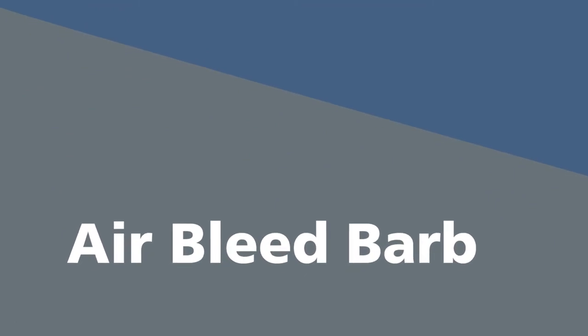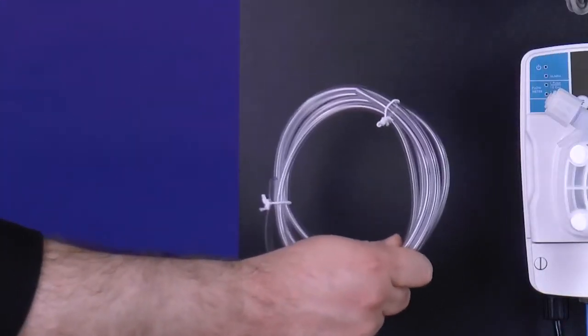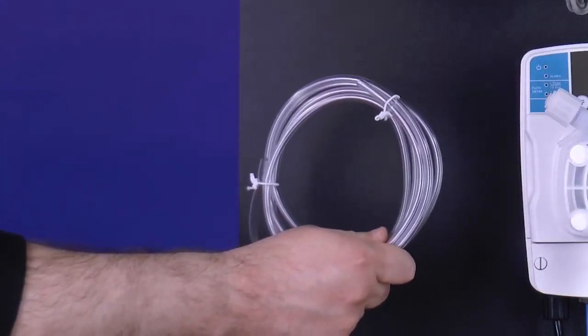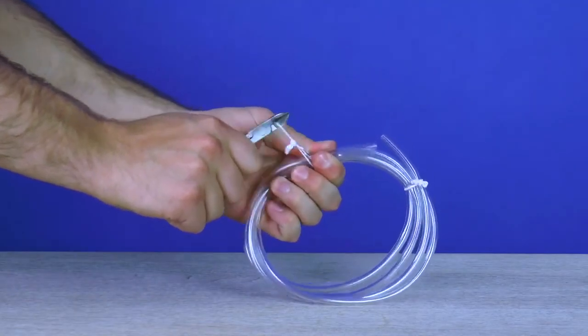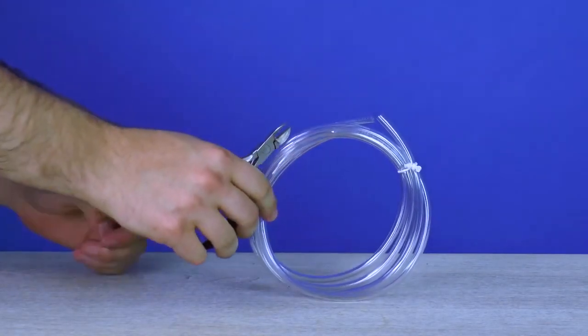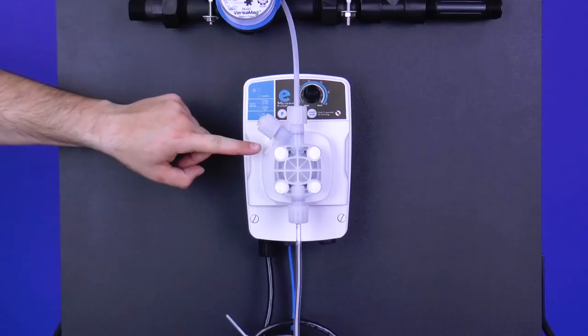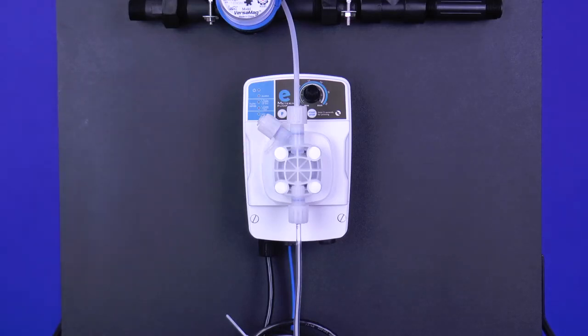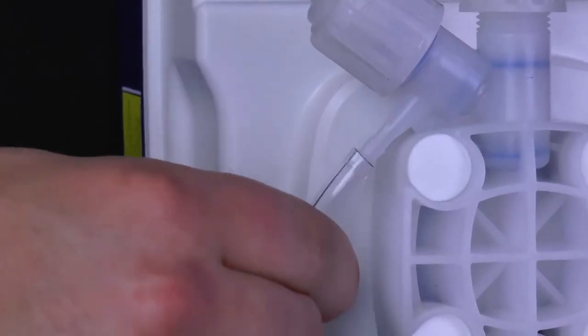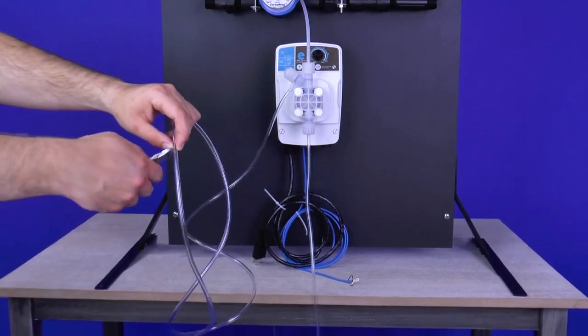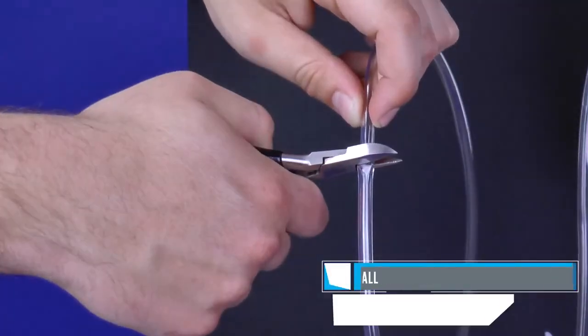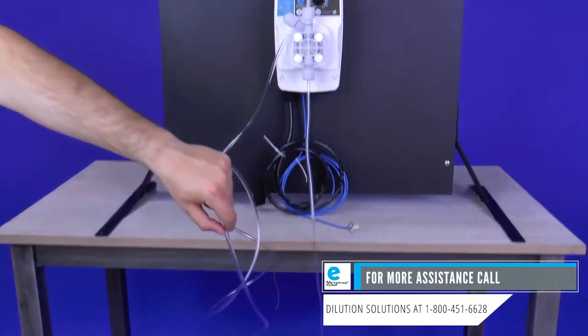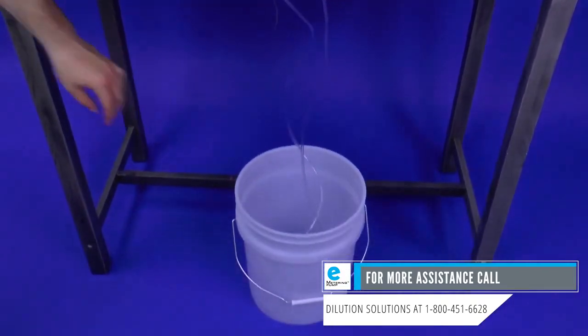Air bleed barb. Finally, take the smaller remaining PVC tubing out of the tubing kit. Using diagonal pliers, cut and remove the string holding the tubing together. Locate the manual air bleed barb on the upper left section of the pump head and slide one end of the PVC tubing over the barb. Use the diagonal pliers to cut the tube so that it is long enough for the chemical bleed off to go into the bucket or stock tank.